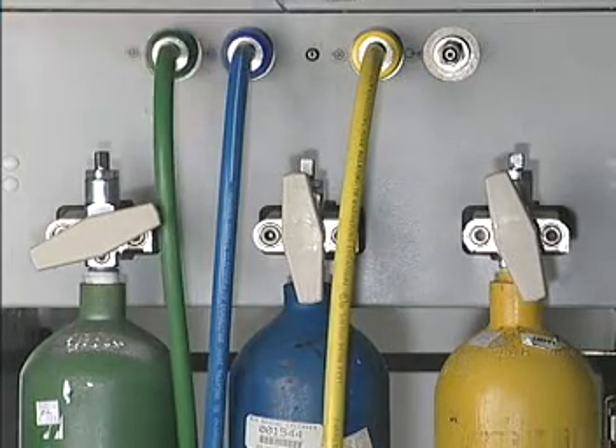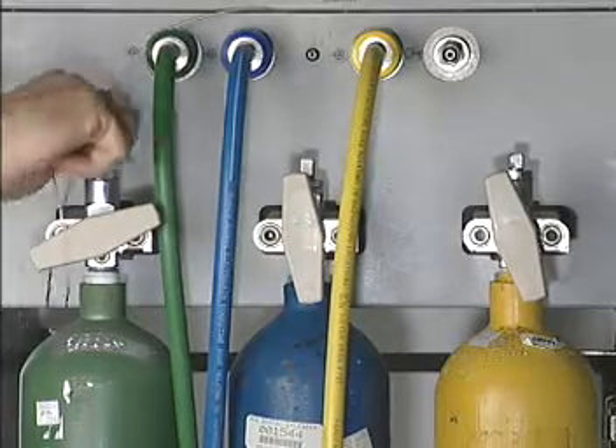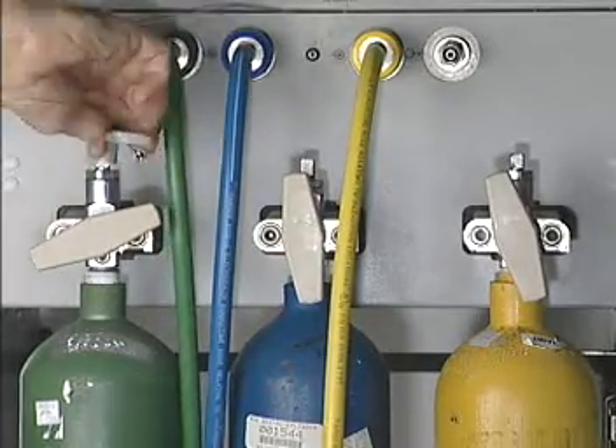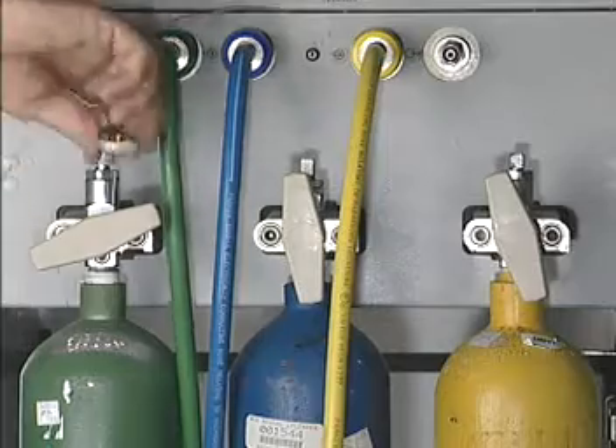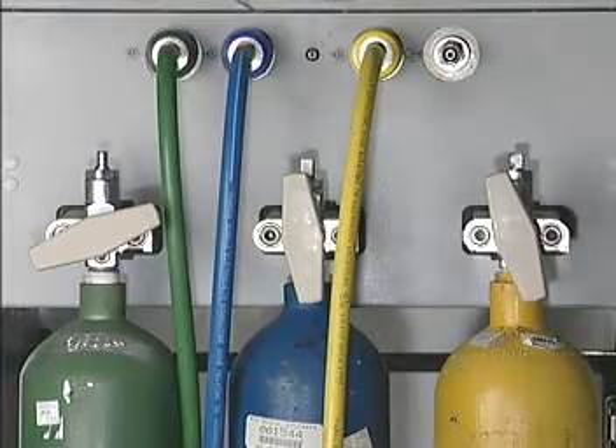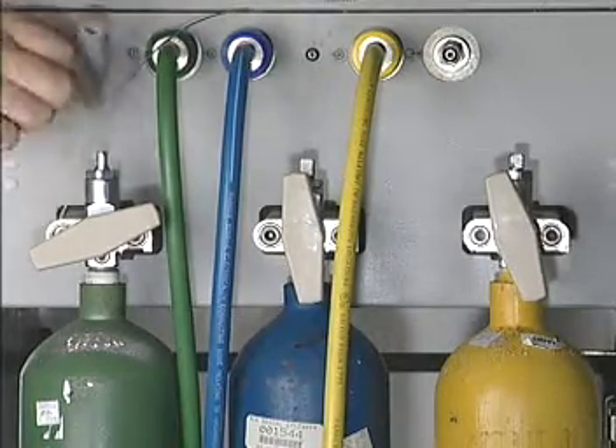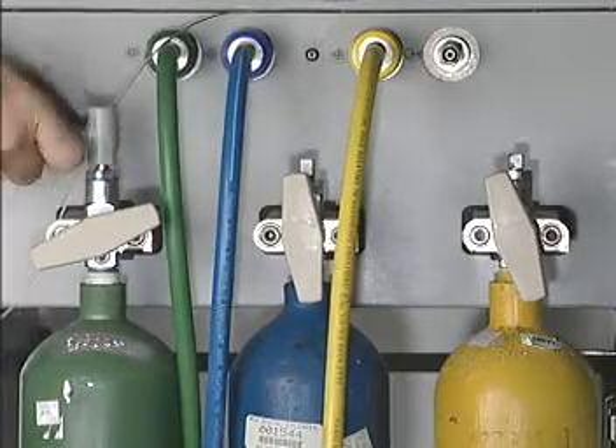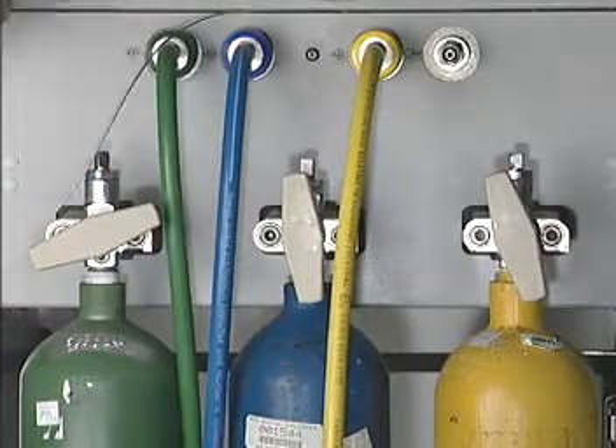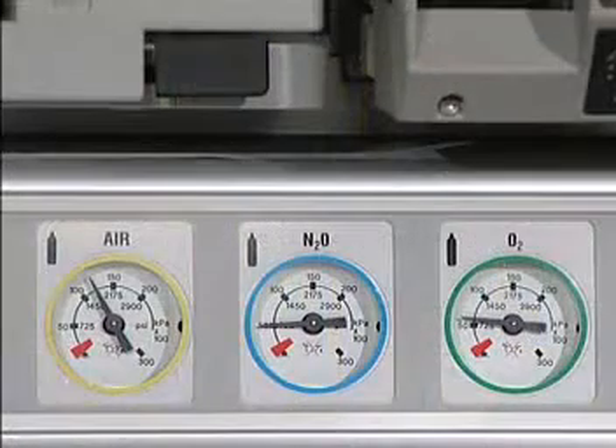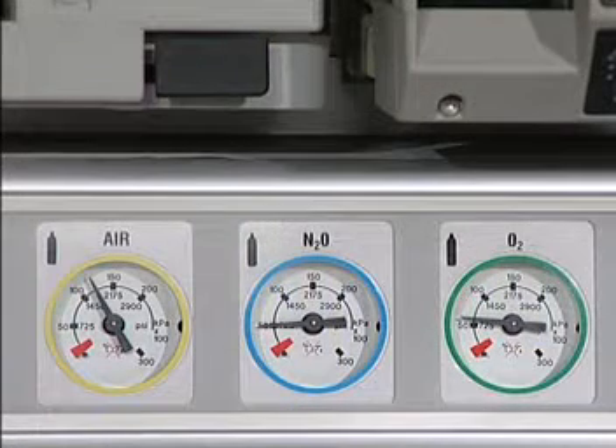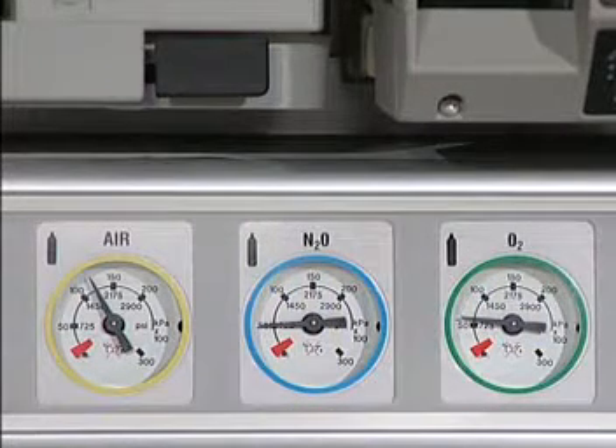Cylinder yokes are available for each of the desired gases. At least one O2 reserve cylinder is mandatory in the U.S. If it is a practice in your institution to close the cylinder valves after checking their contents, which is recommended to prevent draining of the reserve, these gauges may show pressure still present in the connecting tubing only.